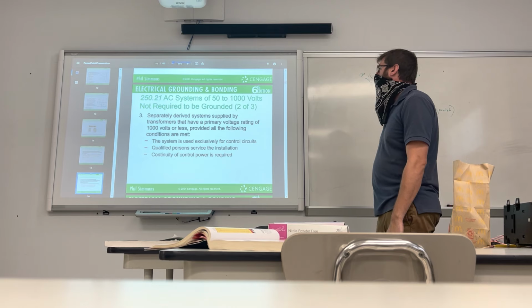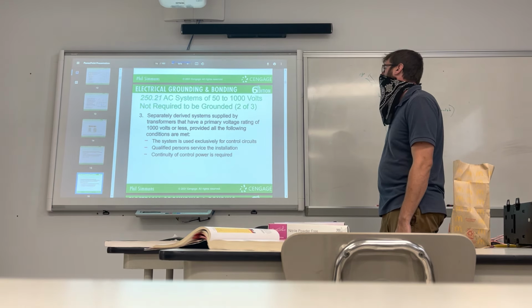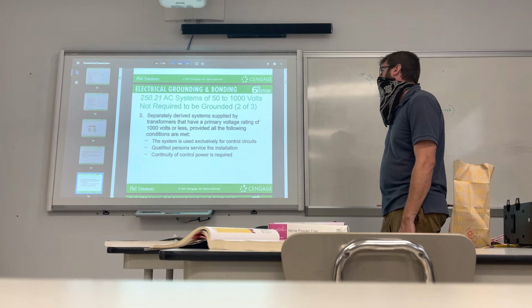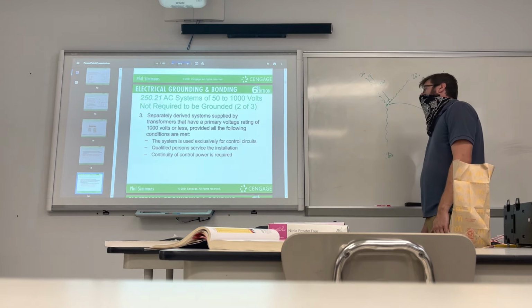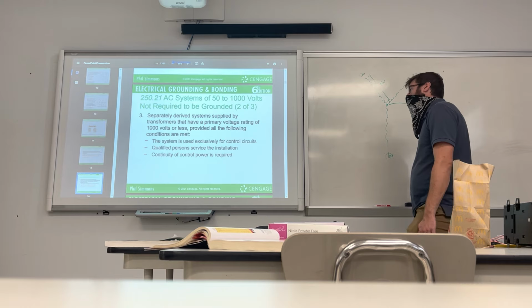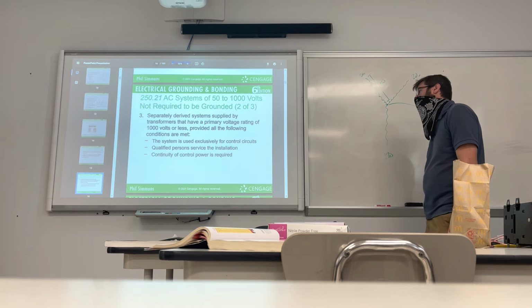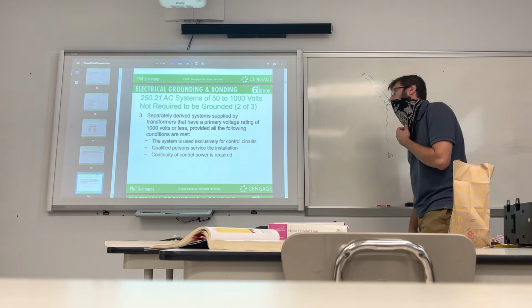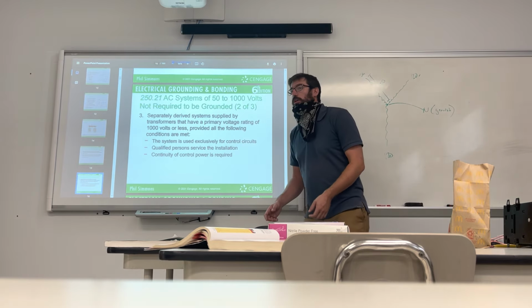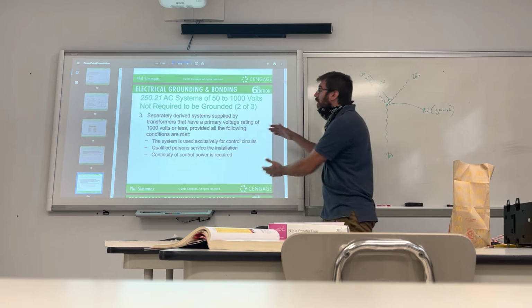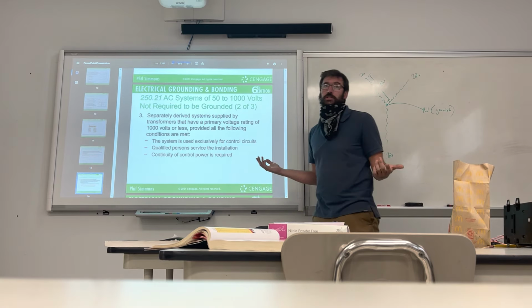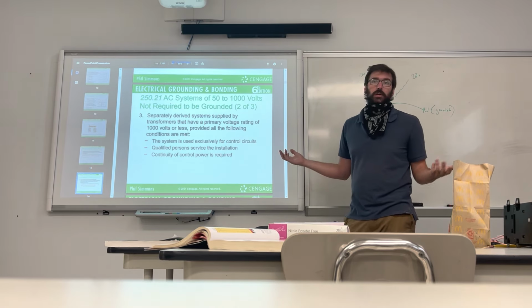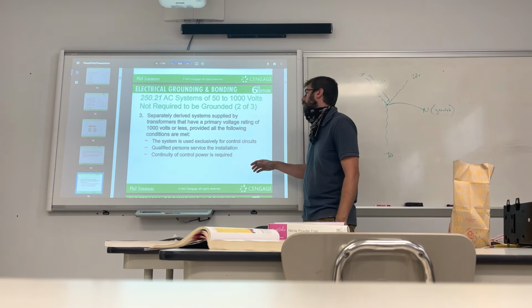Separately derived systems supplied by transformers that have a primary voltage rating of 1,000 volts or less, provided all the following conditions are met. The system is used exclusively for control circuits, qualified persons service the installation, and continuity of control power is required. Yeah, so once again, you don't have to if you have all these available, but what's an easier solution? Ground.